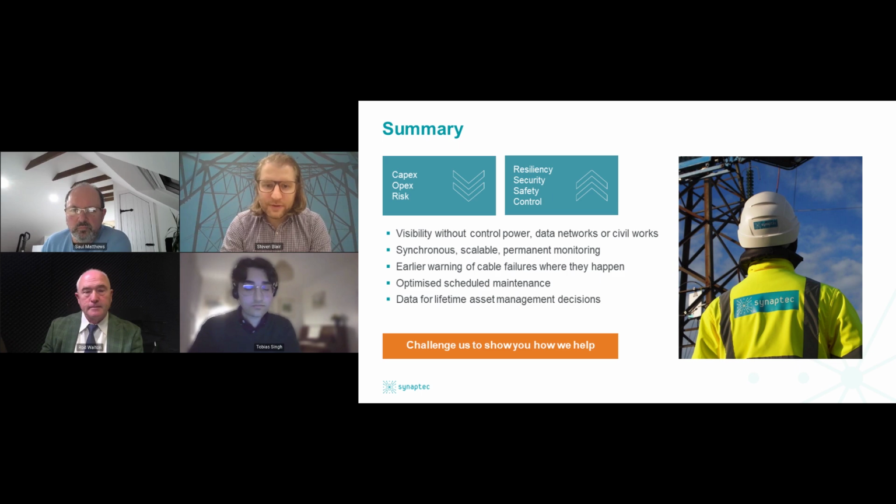Yep, that sounds like a good one for me to jump in and give an answer to. So yes is the short answer, and we have done this for some of our installations. A system that we've retrofitted in the northeast of Scotland here, on a wind farm, where we're monitoring a couple of export cables going out into a wind farm. And what we've done is the analysis work on figuring out everything we've learned from the data, and also we've applied a bit of forecasting capability to that.